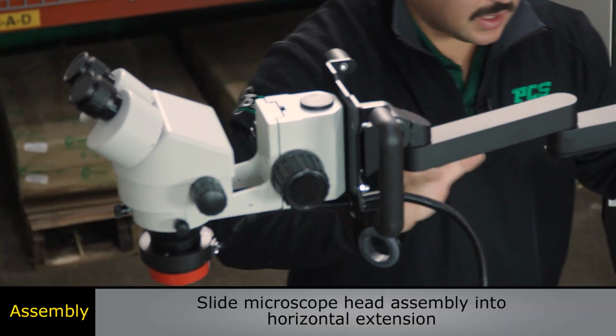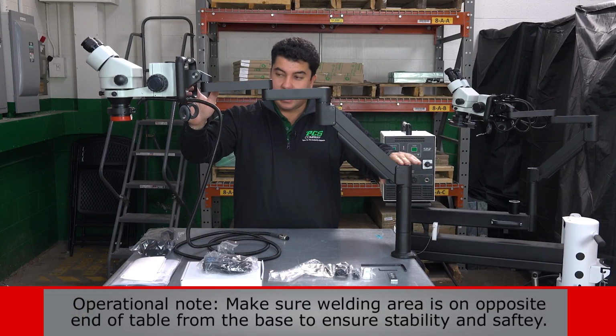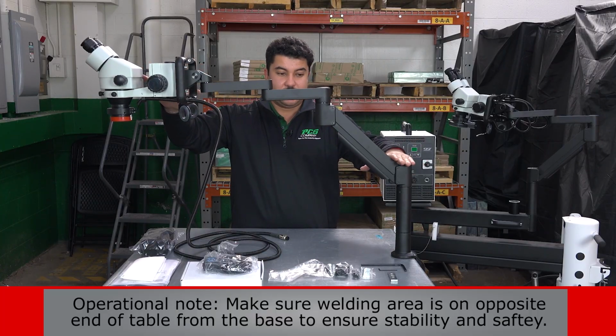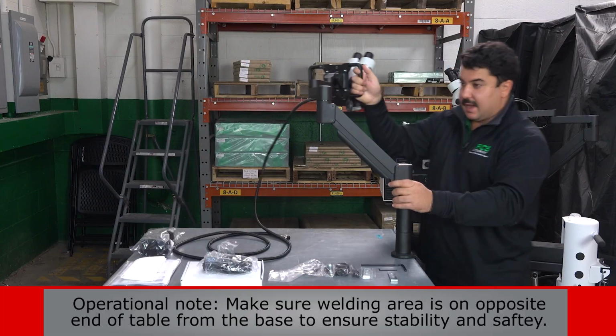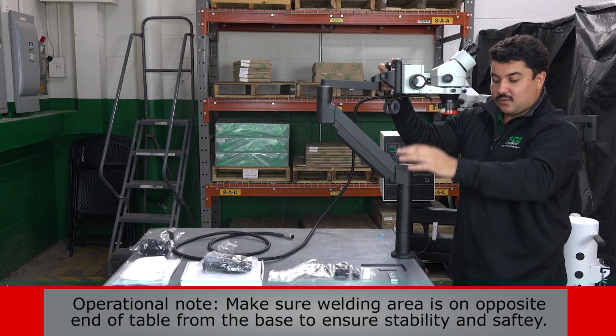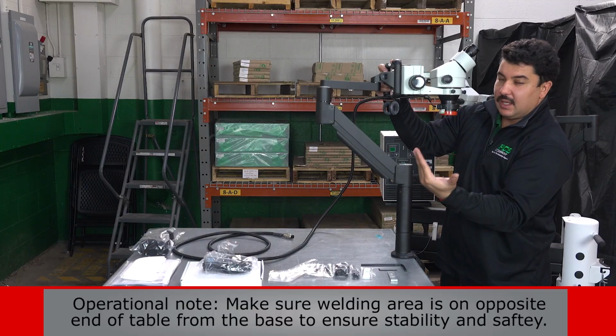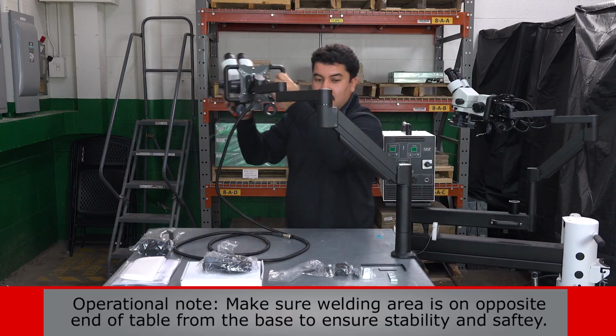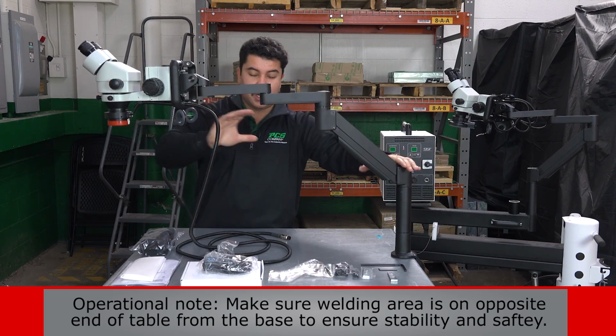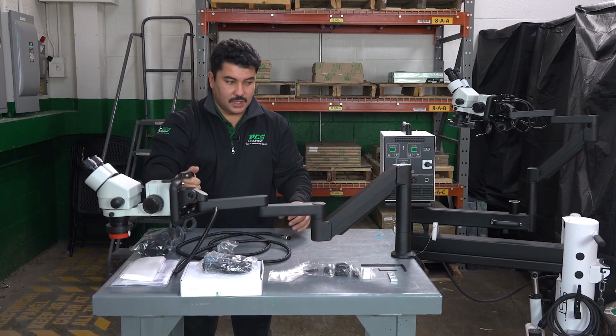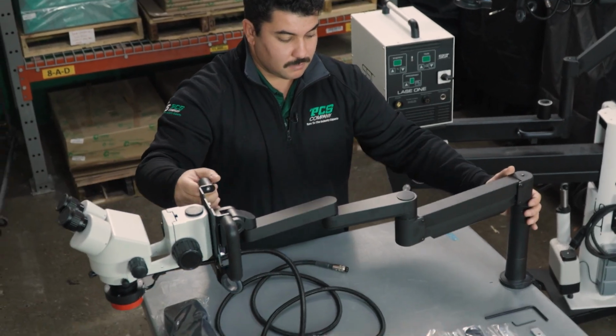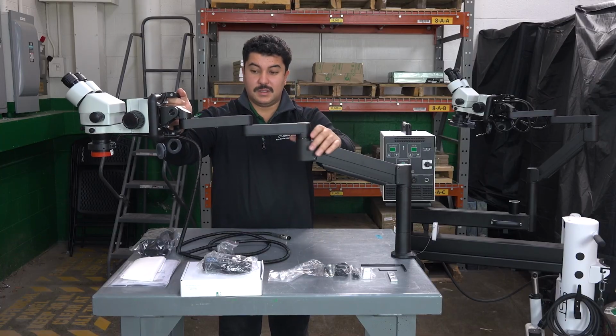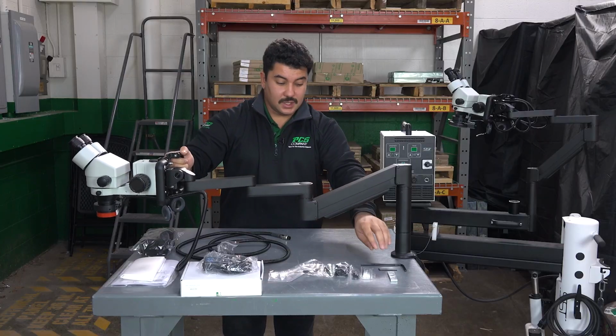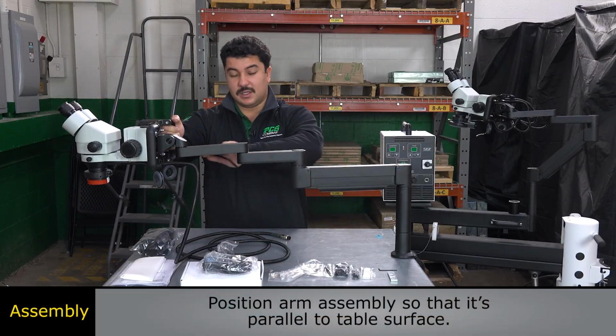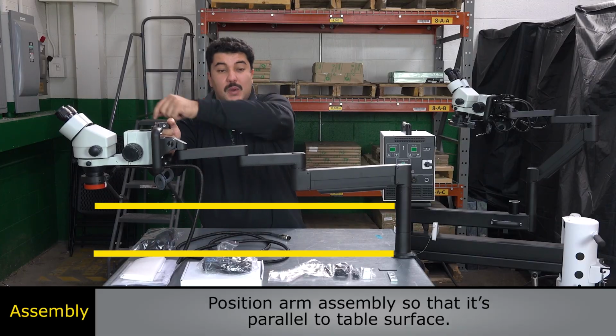All right. You need every time to have the foot and the head at the extreme opposite, because if you weld like that, the weight of the head of the microscope will be on this side and your foot will fall down. So you need to be careful when you are in your office. You need to have the head at the opposite of the foot. All right. So here you can see my arm isn't really strong. So here you need to be at the horizontal with the weight of the head at the opposite.